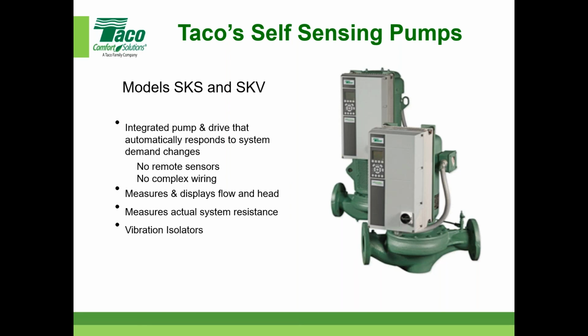And if you specify our pumps with our drives, the drives do come with lead-lag functionality. So if you have an external signal to control the speed of the pump, for example, you can also have the drive determine which is going to be the lead pump and which is going to be the lag pump. So if you have two pumps that are sized for 100% of the capacity, one's operating, the other one's in standby. If one should fail, the second one will start automatically. You can also rotate the pump, perhaps on a weekly or monthly basis, in order to ensure that you have even wear on the pumps, equal hours of operating time. So hopefully, Steve, that answers your question.